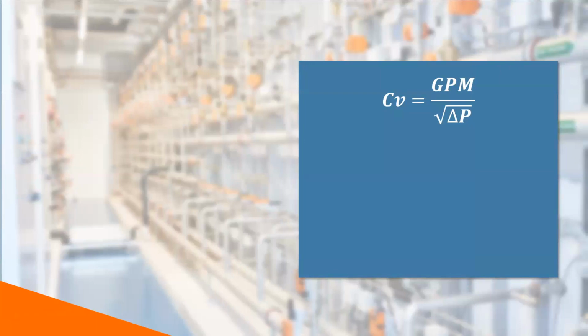Okay, so GPM is typically the max GPM of the coil or heat exchanger. Pressure drop is figured in one of three ways. Flat specified, a fixed value from a design or consulting engineer. This is most common and typically is between 3 to 5 PSI, which is your ASHRAE standard. Selected based on the pressure drop of the coil or heat exchanger. The pressure drop would be greater than or equal to that of the coil, or pressure drop is determined by valve authority. Of these three ways, the first two are wrong most of the time. And the last one is impossible with the information given to the controls contractor that is selecting the valve.